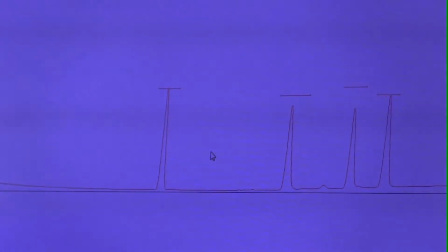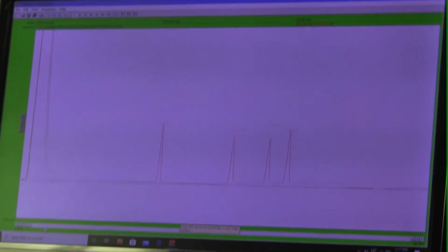So now we're going to see what the sample looks like. And I'm also going to click on channel details, and I'm going to say overlay the data that's in channel 2, and that way we can see the calibration chromatogram ghosted in the background, while the chromatogram from the sample that we're running right now appears in black on top of the red overlay. So it's important to understand how we arrive at the answer in the units of percent, right? Because we did get an answer when we did the calibration. We got an answer that was 13.32%.